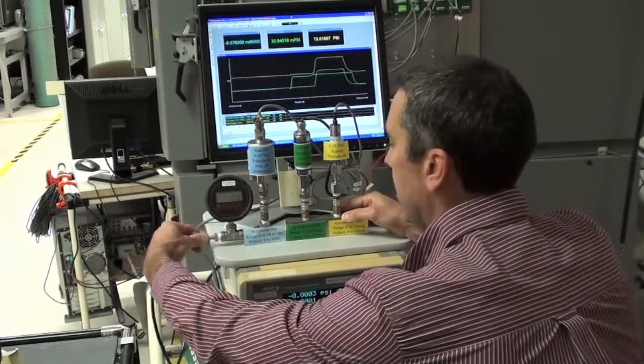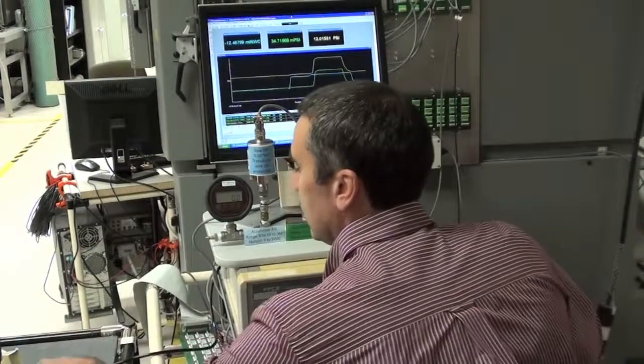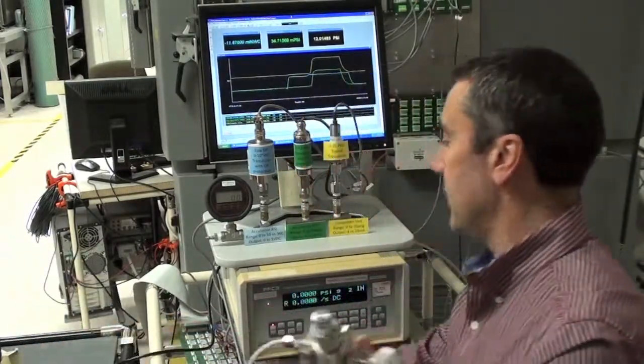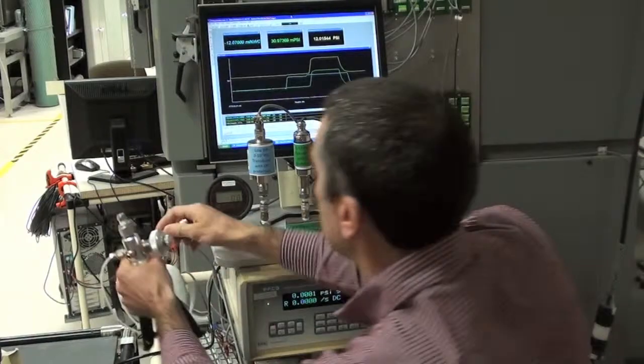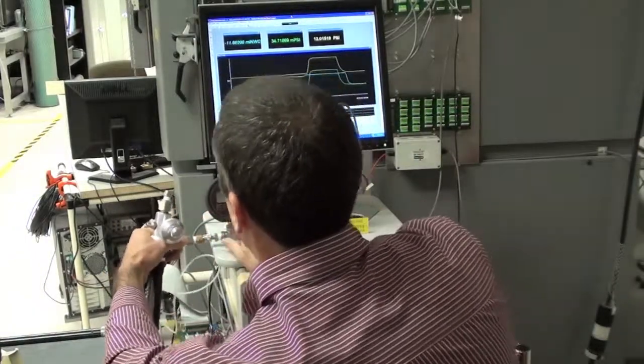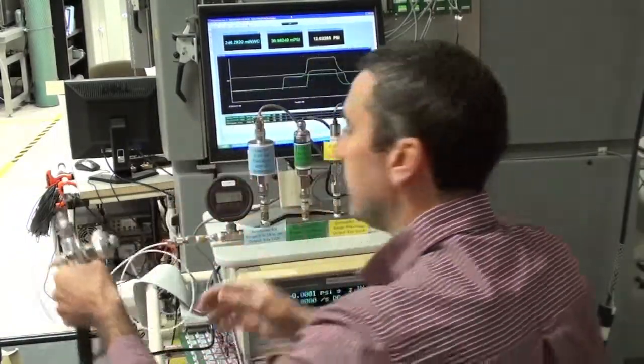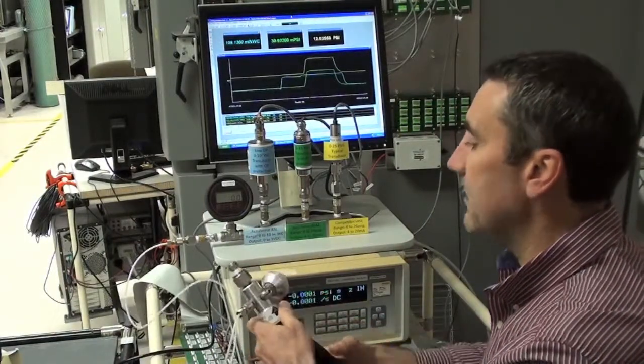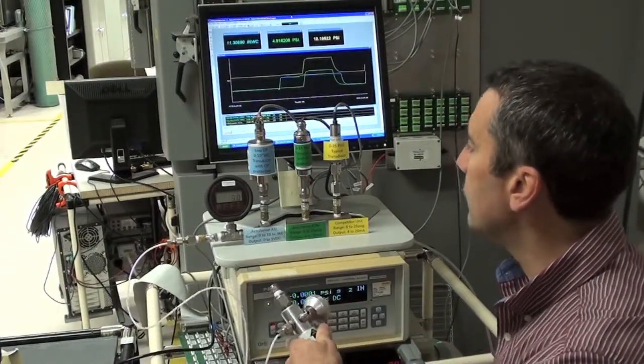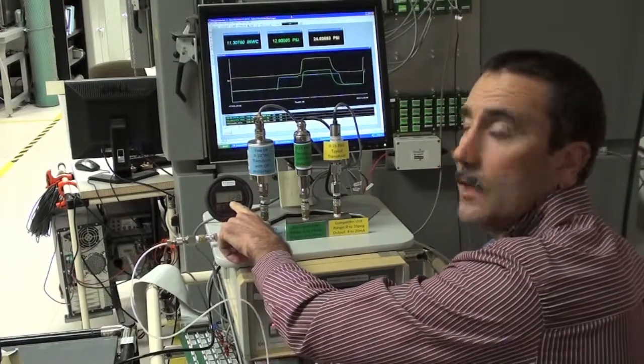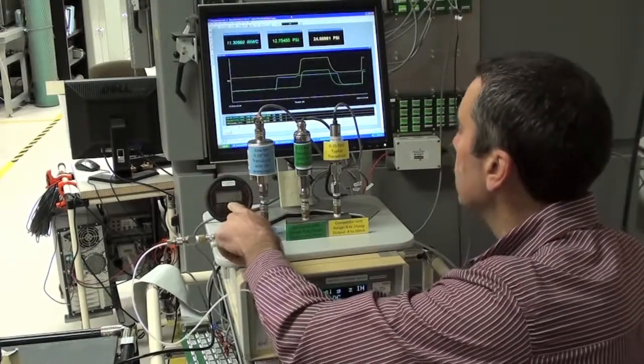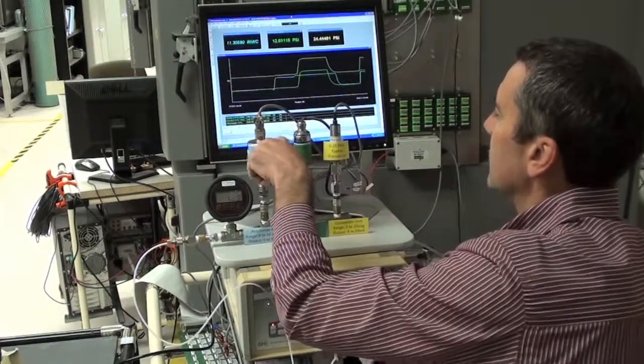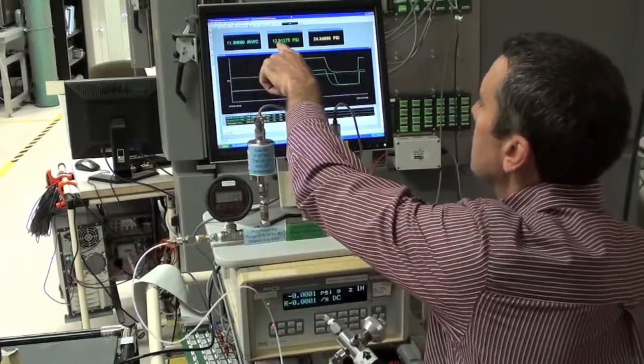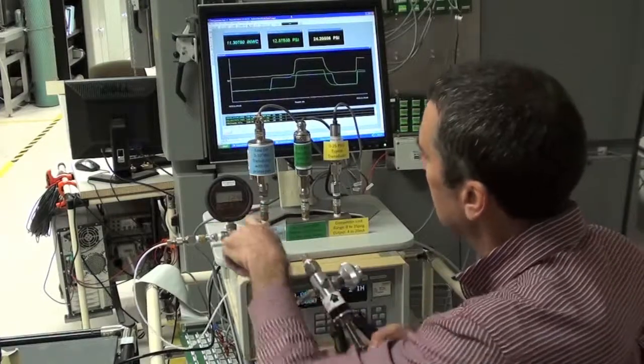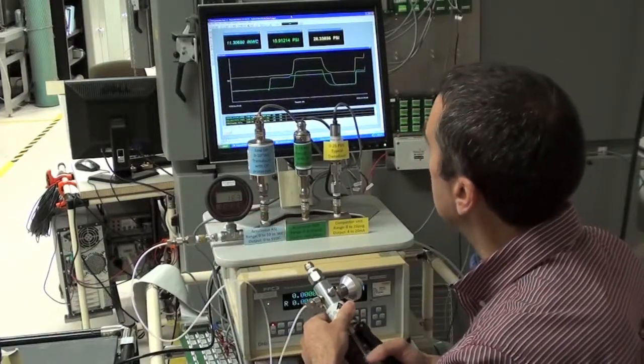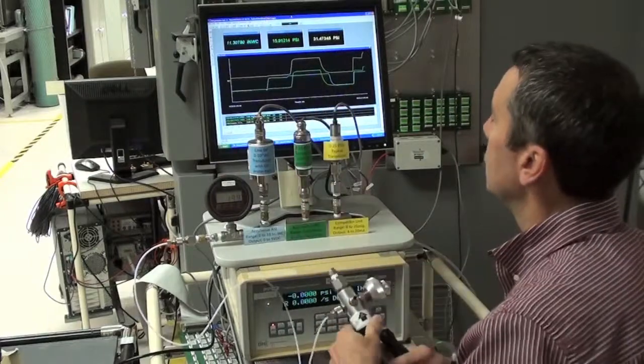Now I'm going to subject this to a high overpressure condition. I'm going to detach it from our pressure controller because it cannot generate very high pressure the way it's configured right now. I'm going to attach a simple hand pump to the manifold, and I'm going to pump and apply pressure. You can see the digital gauge is now recording the pressure. It's about 12 psi. I'm already saturating this transducer, and you can see this one is recording 12 psi as the gauge, and now I'm over 15, so that one's saturated.